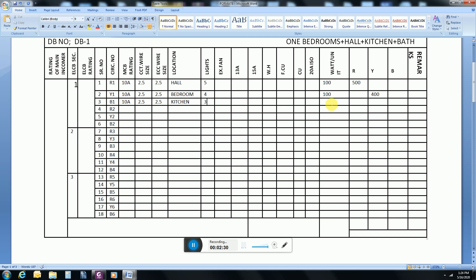For kitchen, three lights are enough. Each light is 100 watt, so the total load will be 300 watts. There will also be an exhaust fan at 100 watt, so the total becomes 400 watts. For the bath, there are 2 lights and 1 exhaust fan, each 100 watt, so the load on the yellow phase will be 300 watts.